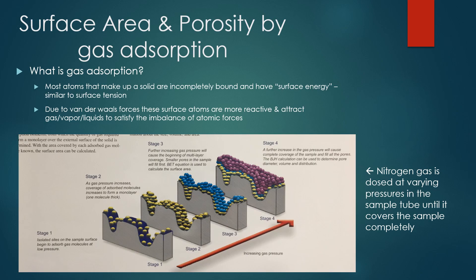What does this instrument measure? It measures surface area and porosity of solid materials through the process of gas adsorption. Think about it similar to surface tension - materials have this surface energy. The atoms on the edges, due to van der Waals forces, are more reactive in that they want to attract gas to satisfy their imbalance of atomic forces.